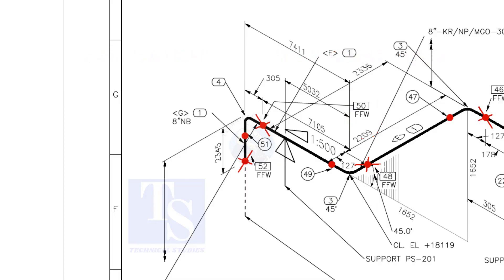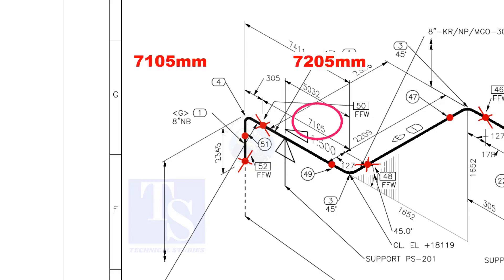An additional length of pipe is added to the calculated dimension. Add an FFW for Field Trim Allowance. As per the drawing, the length of this pipe is 7105 millimeters. But we will fabricate a minimum length of 7205 millimeters pipe.